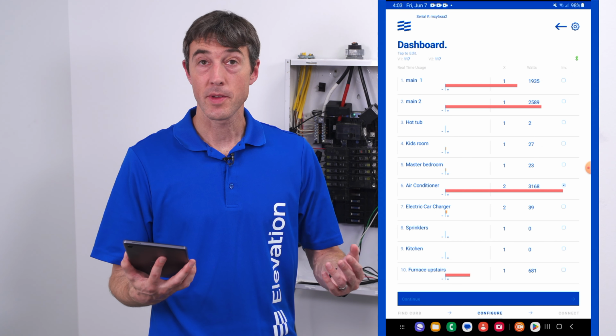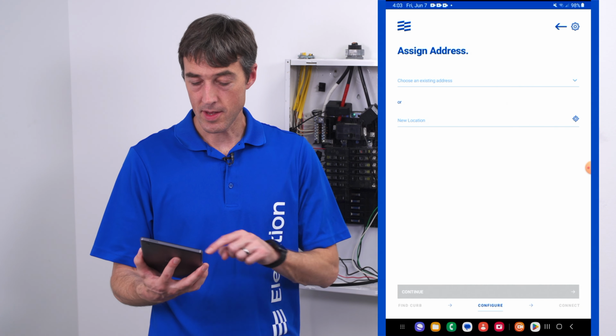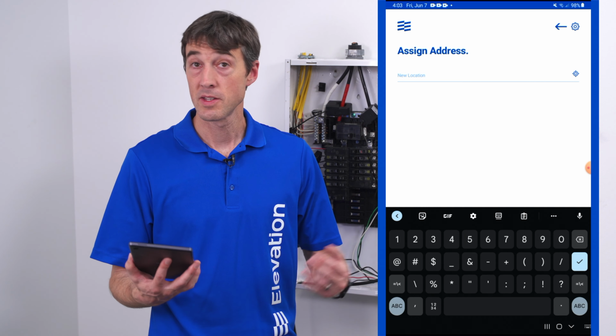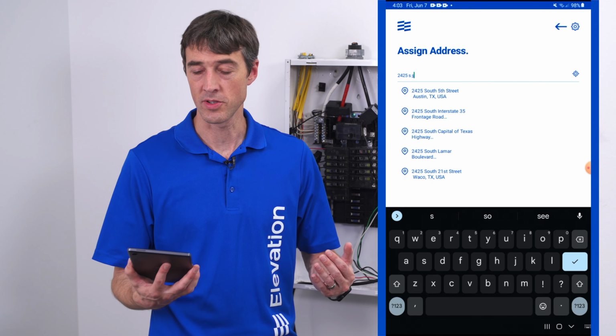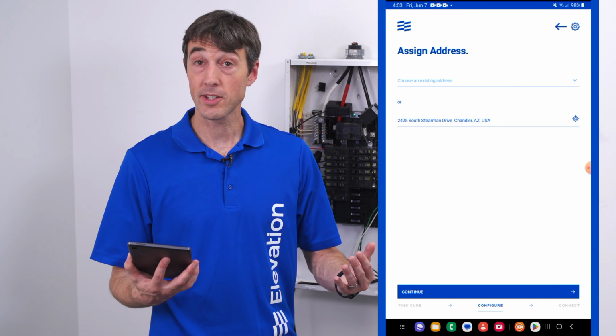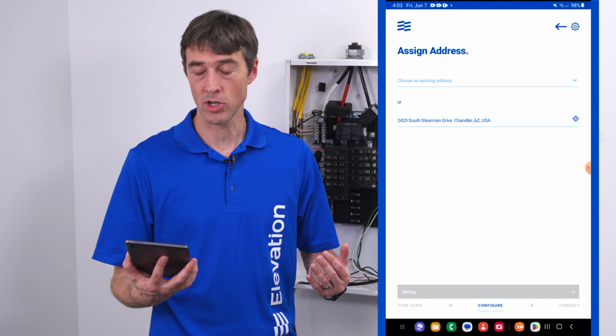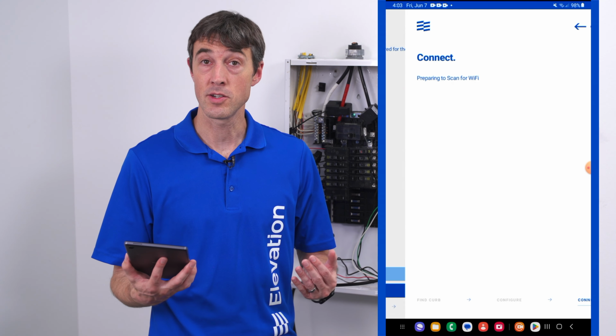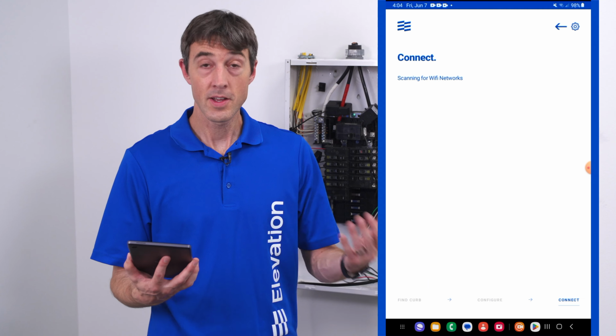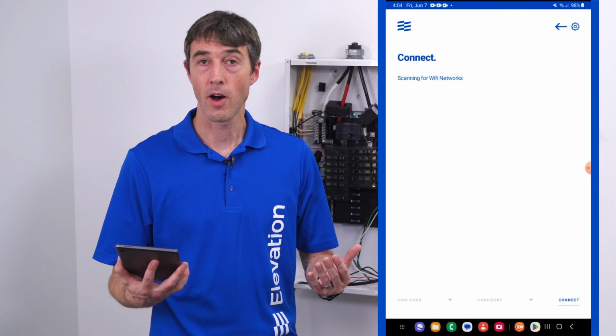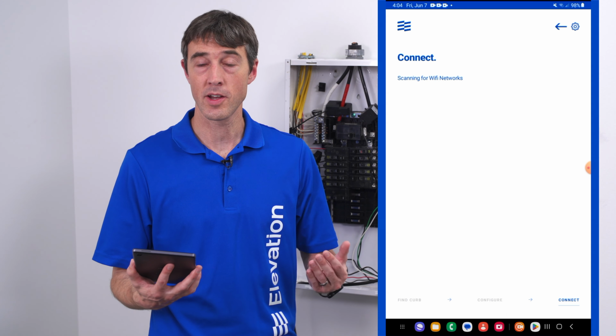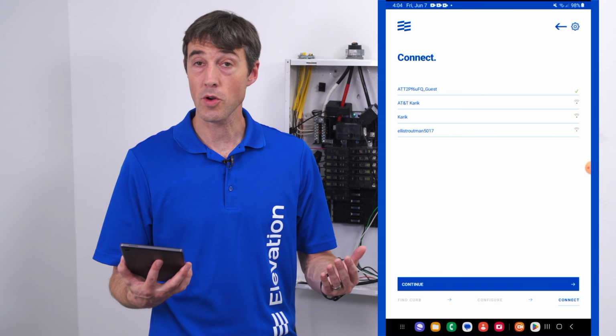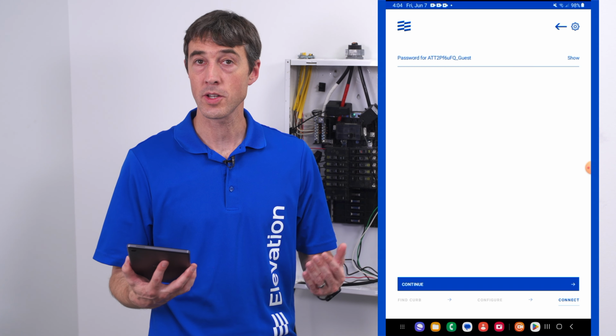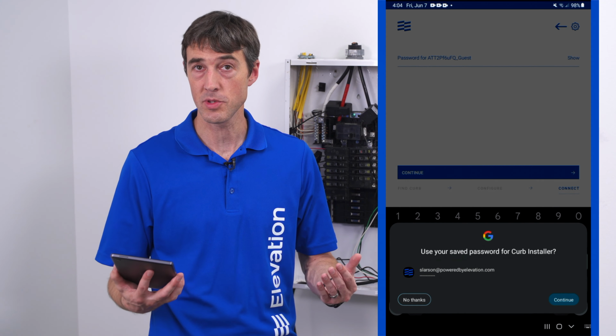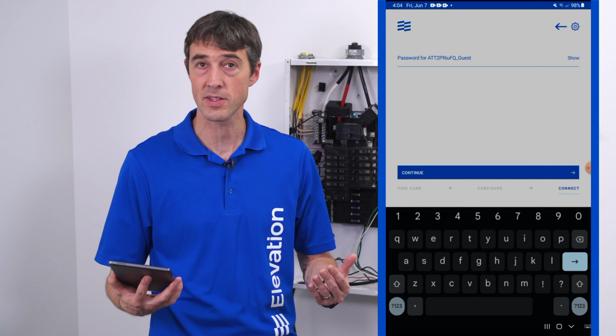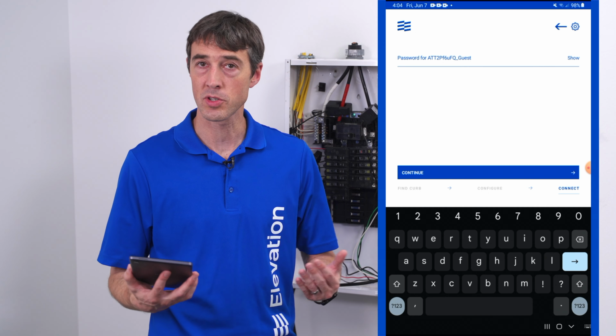The next step in configuring the Curb device is identifying the location. Simply put in the address where the Curb is installed. The next step of getting the Curb configured is getting it connected to the customer's Wi-Fi. Scan for Wi-Fi on site and then put in the customer's password. It's worth noting that Curb only works on 2.4G systems. It will not work with a 5G system. This is very common for most smart home devices.